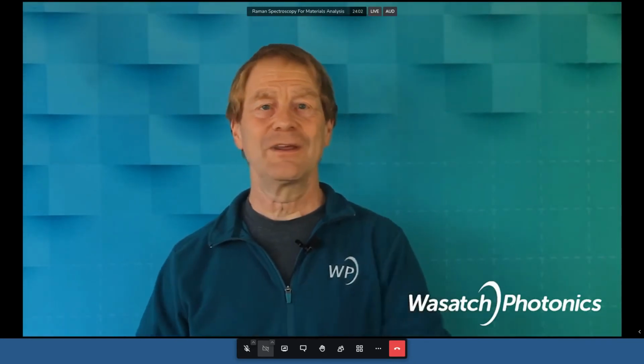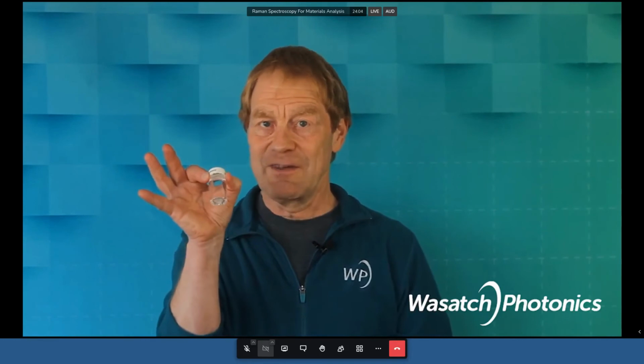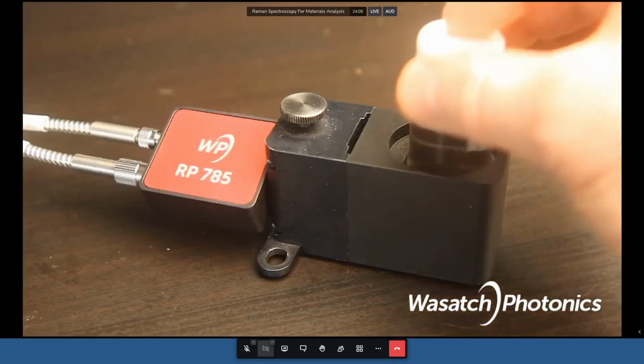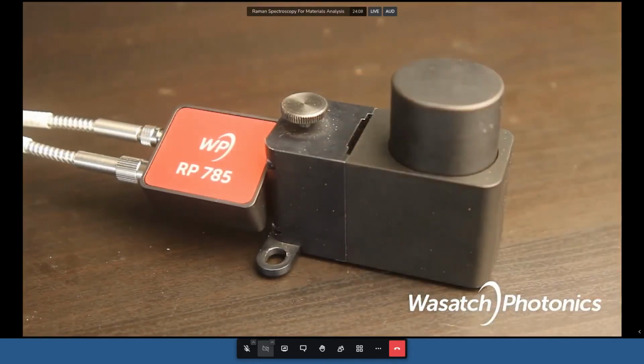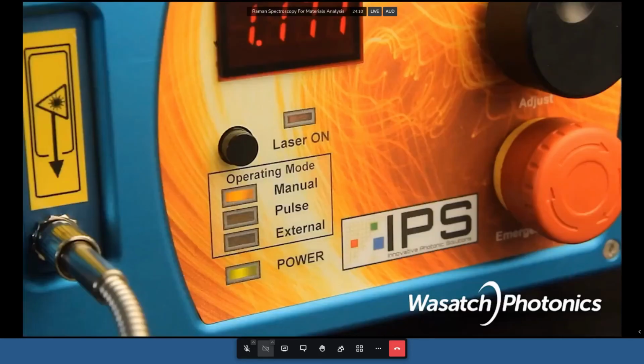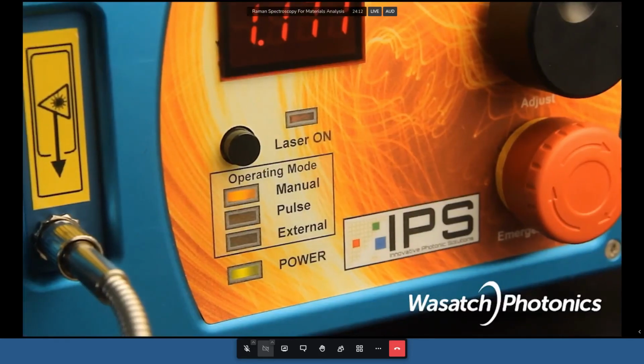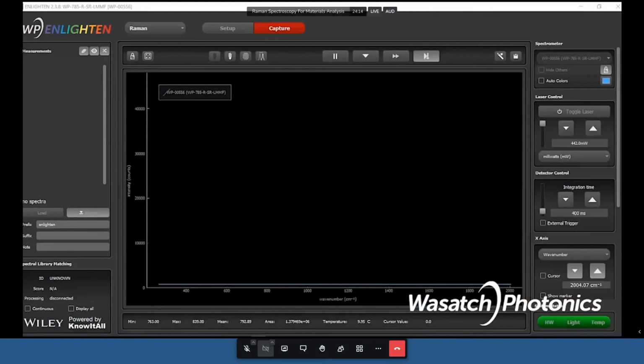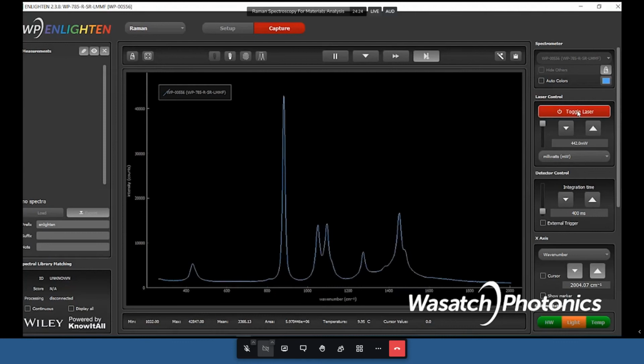Now we're ready to take a measurement. So take your sample, insert it into the sample holder and cover the sample holder. Then turn on the laser. For external lasers, push the small button on the front. For spectrometers with integrated lasers, use the Enlighten software to turn the laser on. After a short required safety delay, the laser starts up and, oh, beautiful!